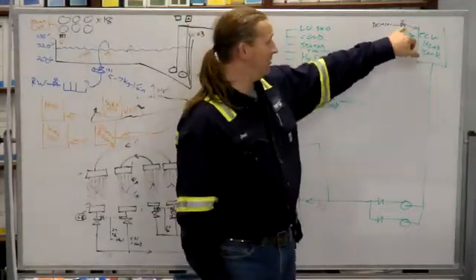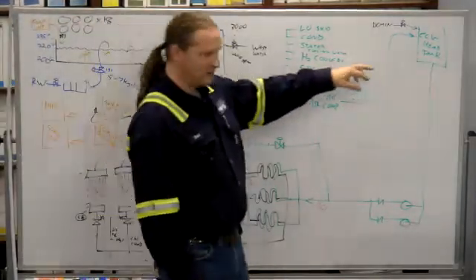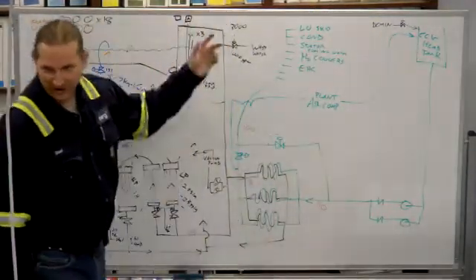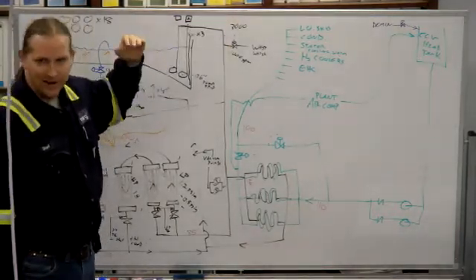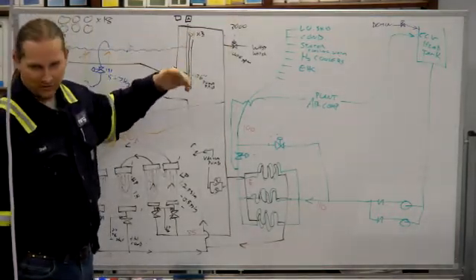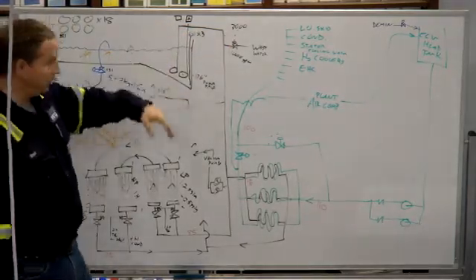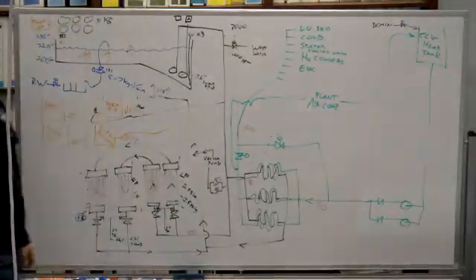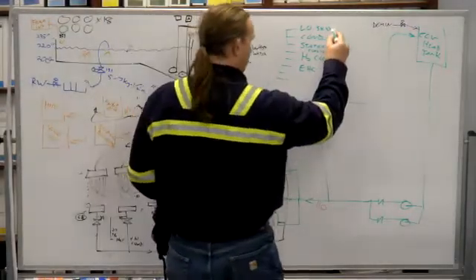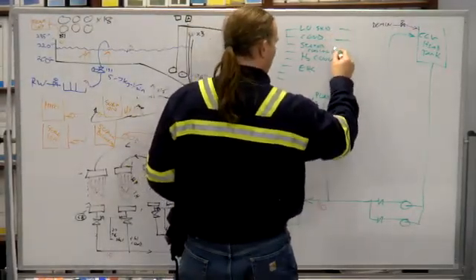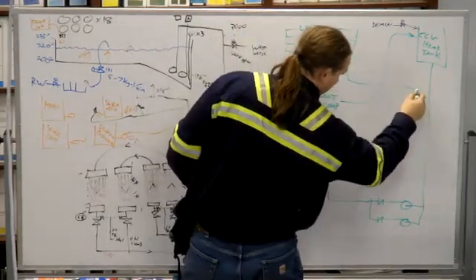This head tank, this valve is not open very much. It does a batch add like once every three days or once every five days or something like that. So that level will sit there at 80 and you'll take your rounds and it might be an inch lower or two inches lower. And then eventually it gets down to around 60 and then it fills up and it adds 20 inches back to it. All the rest of this water-cooled stuff comes to another header and goes back to the pumps.